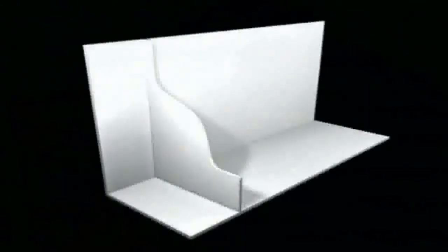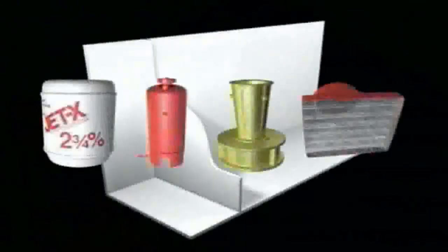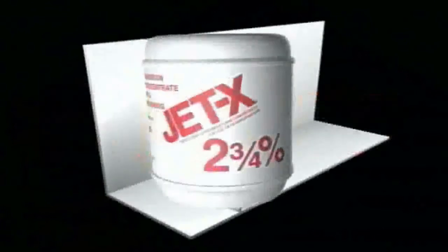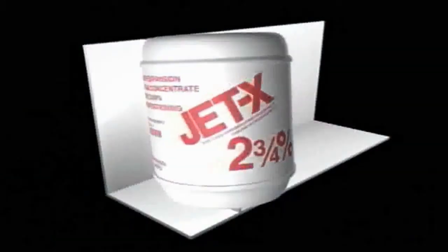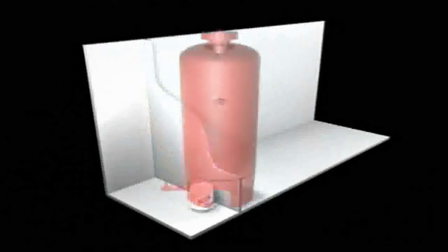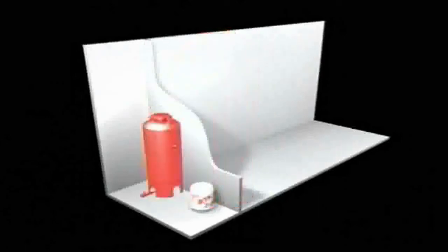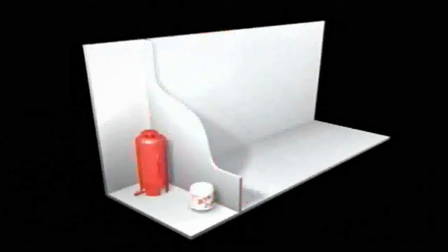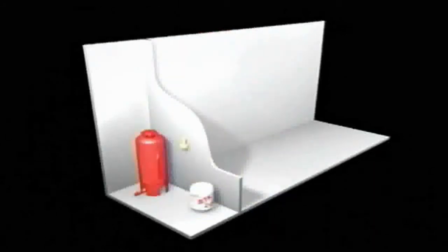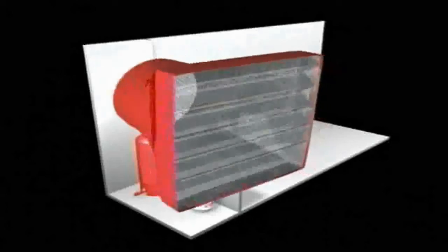The typical high expansion foam system consists of four major components: Jet-X high expansion foam agent, a bladder tank sized to fit the application, a foam proportioner, and one or more high expansion generators.